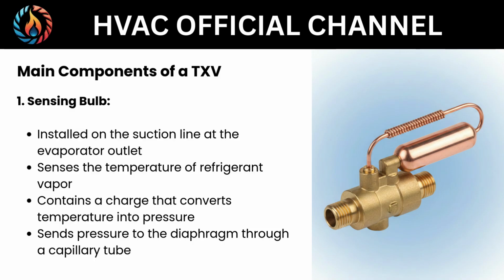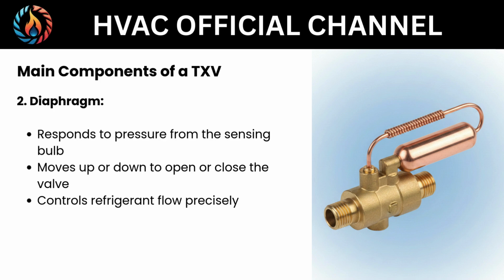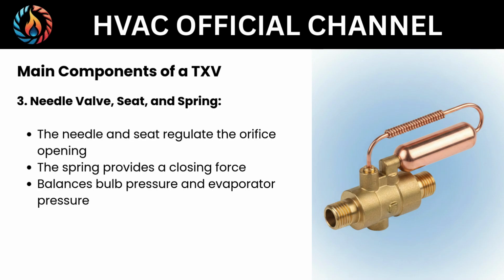Main components of a TXV. 1. Sensing bulb. Installed on the suction line at the evaporator outlet. Senses the temperature of refrigerant vapor. Contains a charge that converts temperature into pressure. Sends pressure to the diaphragm through a capillary tube. 2. Diaphragm. Responds to pressure from the sensing bulb. Moves up or down to open or close the valve. Controls refrigerant flow precisely.